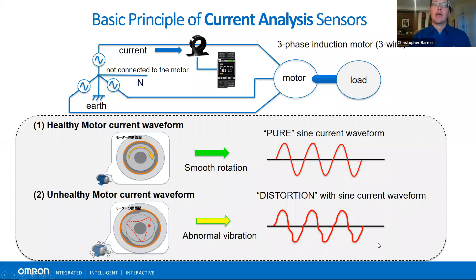You can see this is an unhealthy motor, and again, it's subject to human interpretation. All the data or the sensors will tell you is that something's going wrong. You can see it in the form here, and have it trigger an alarm, but to work out specifically what's going wrong, you'd have to go look at the motor, because it could be one of these major factors, anything from problems with balancing, the coupling, or insulation resistance. So it won't tell you exactly what's going wrong, it'll just tell you, hey, it's a symptom. It's almost like as a human, you can read you've got a fever, you don't know if that fever means you've got COVID-19 or something else.